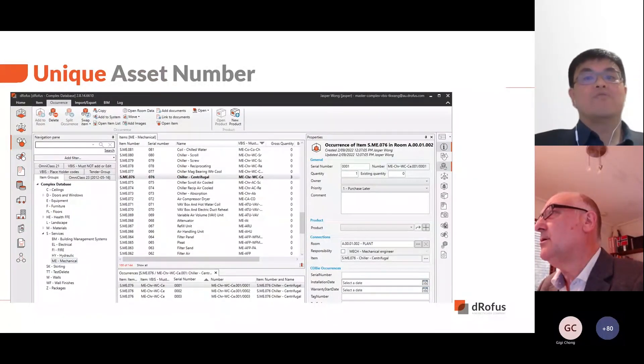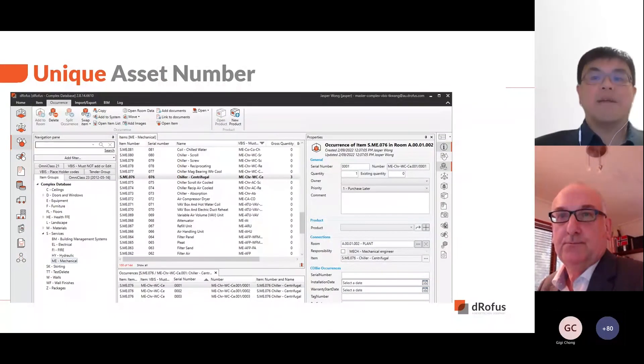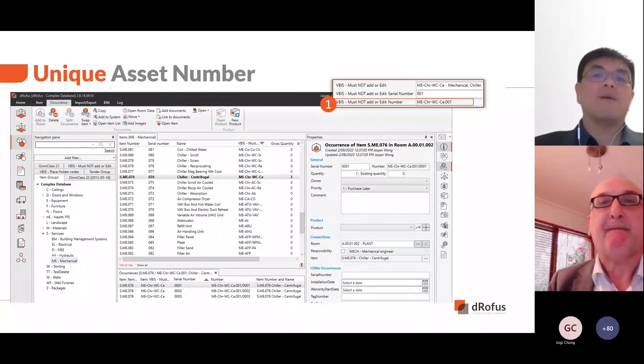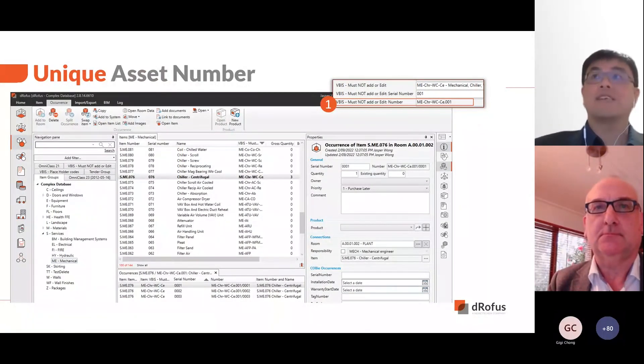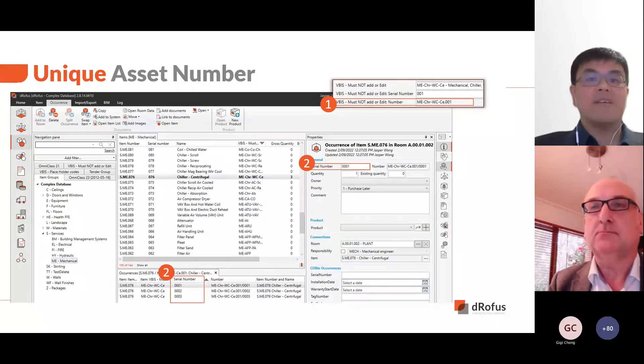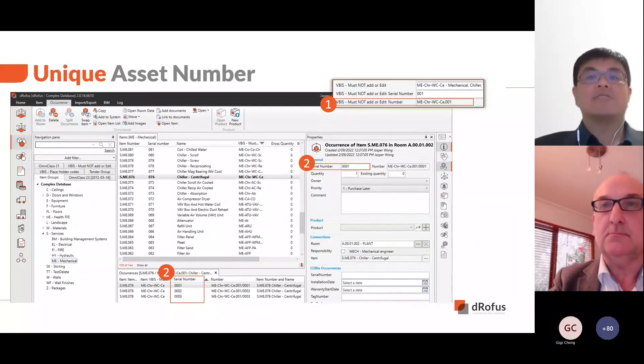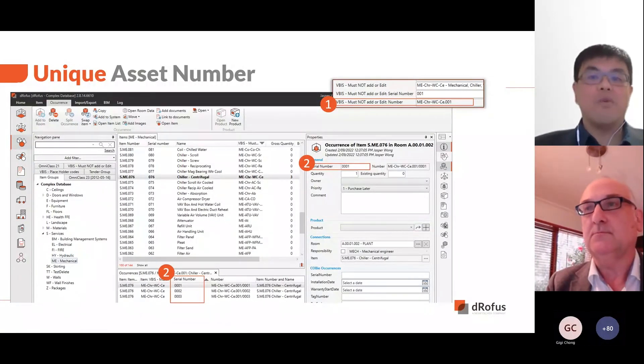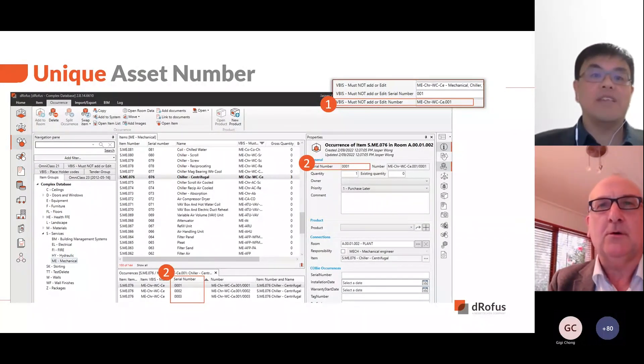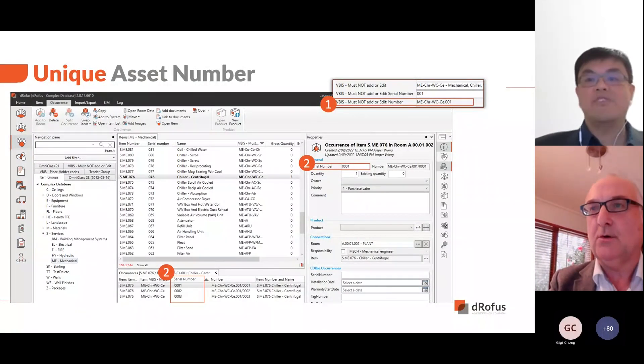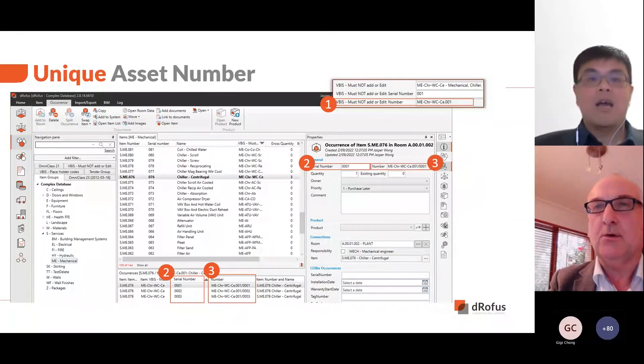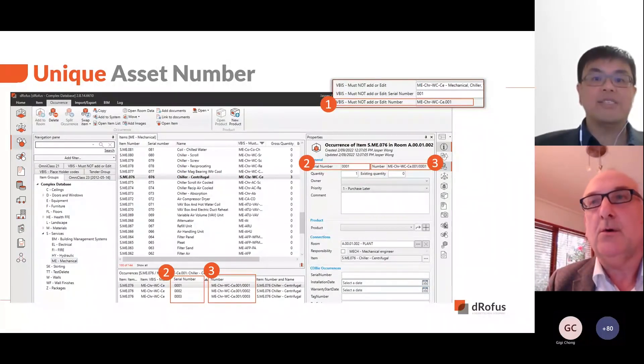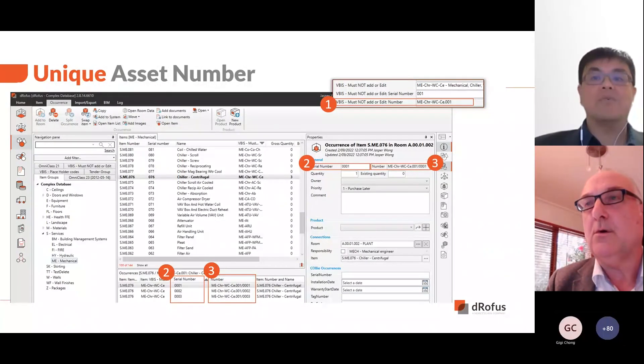This unique asset number is made up of two parts. The first part is a classification number — a combination of the VBIS classification and a unique number generated for that classification. The second part is a serial number, where each occurrence is automatically assigned a unique serial number. In the design phase, you may have occurrences with quantities of more than one. These occurrences can be split into individual instances and unique serial numbers will be generated. Combining the classification number and the serial number generates the unique asset number. Looking at the three centrifugal chillers, each one has a unique asset number which you can now use on your project.